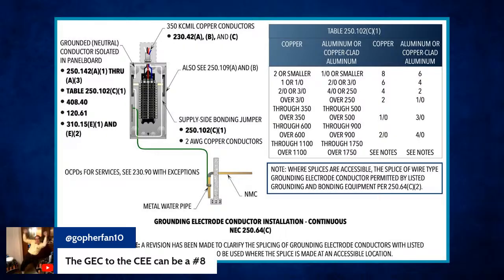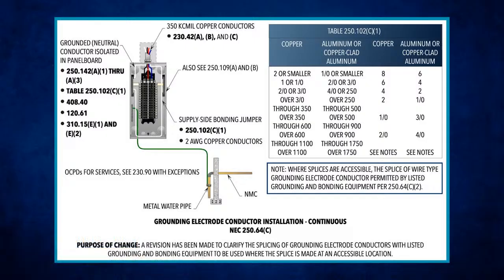Yeah, and this is where Weedman doesn't get it, because he's trying to say that the grounding electrode conductor to the concrete encased electrode can be a number 8. Dude, they're not going to do that, dude. That is so stupid. They're not going to try to encase copper in the concrete and be like, okay, we're going to bend up a rebar, then go like 3 foot of number 8 to the panel. He's not been in the field, so it really shows. And I'll show next week what was said. Like I say, you might not have been able to hear it this week, but you'll hear it next week.